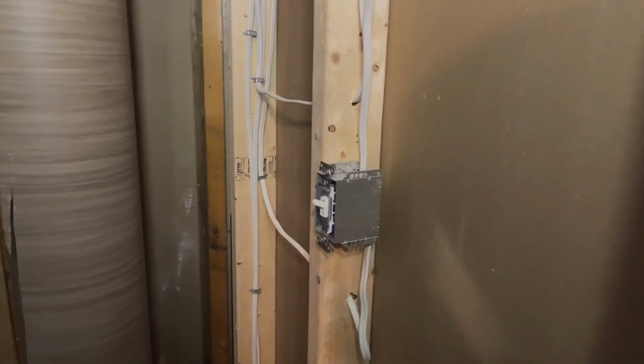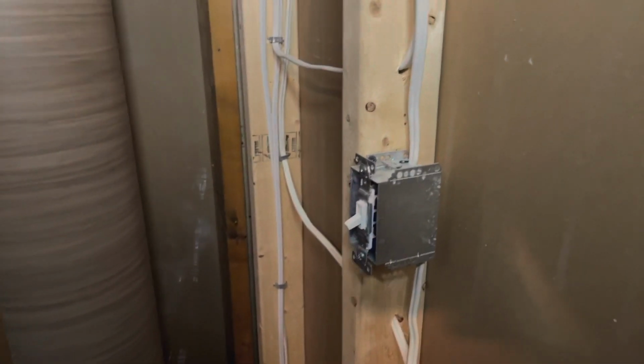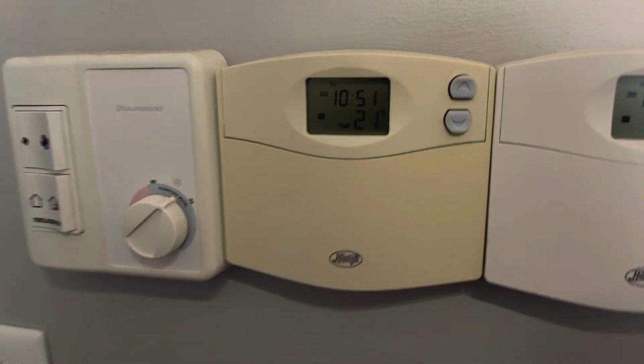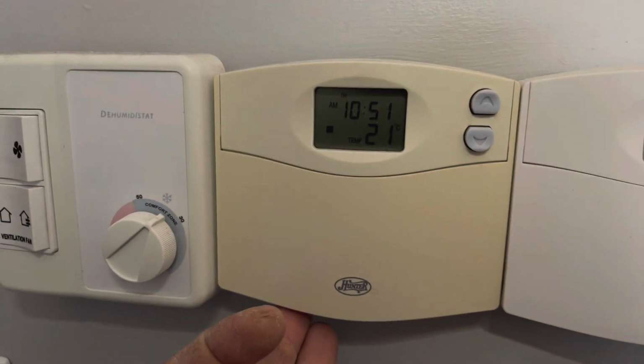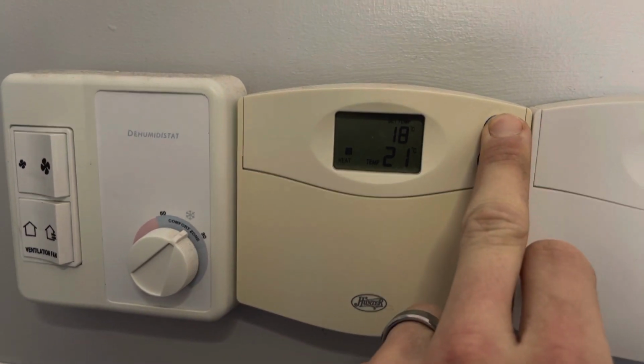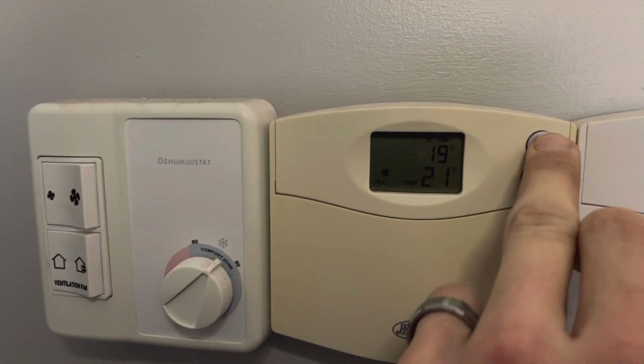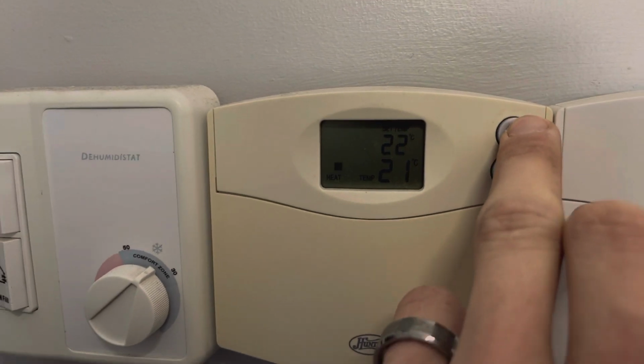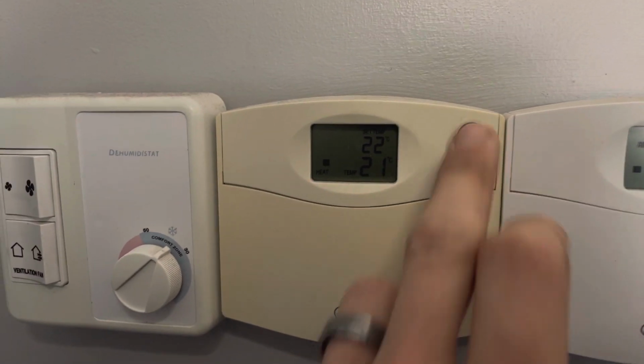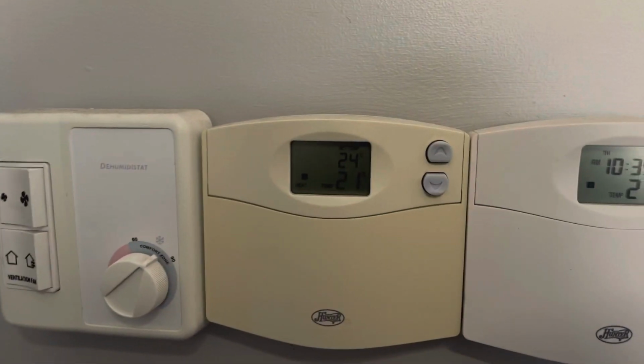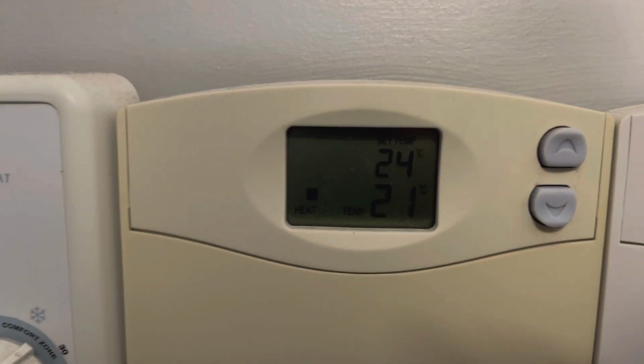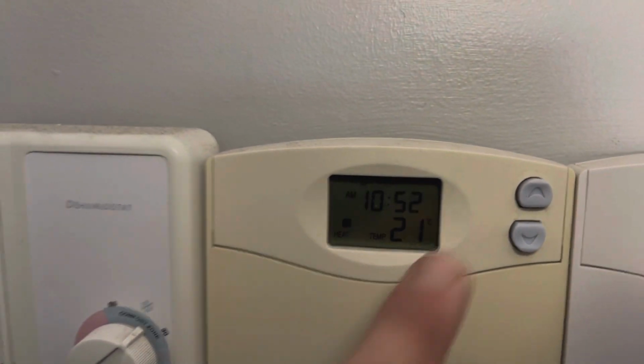First thing. Then before you get into anything with your furnace, find your furnace switch and shut it off before you do any electrical work. And one of your main issues with your furnace could be your thermostat itself. So you want to make sure that your temperature is set higher. We have it low because we have a pellet stove, so we try not to have it come on, but just set it even really high to make sure that when you flick the switch back on to test the furnace, that it calls for heat.